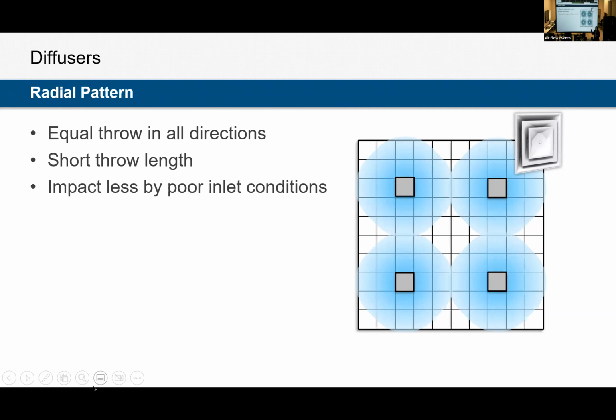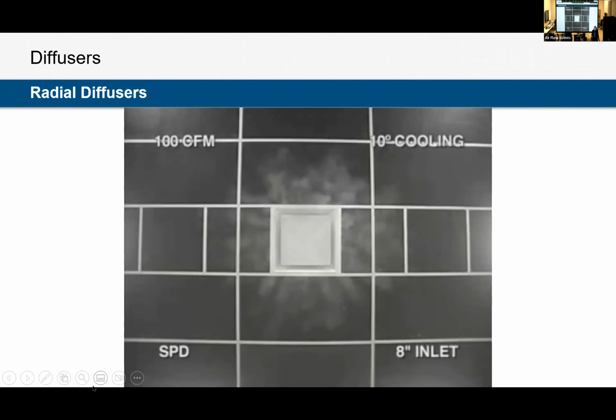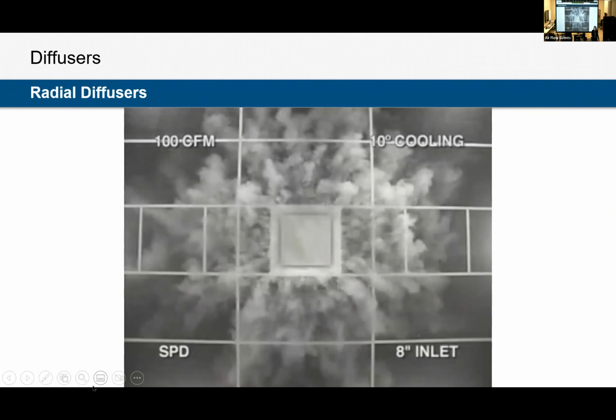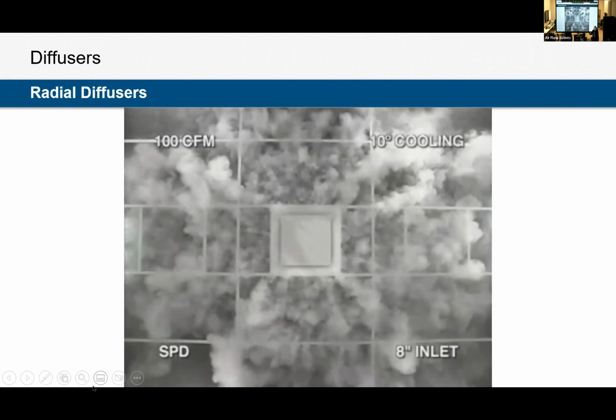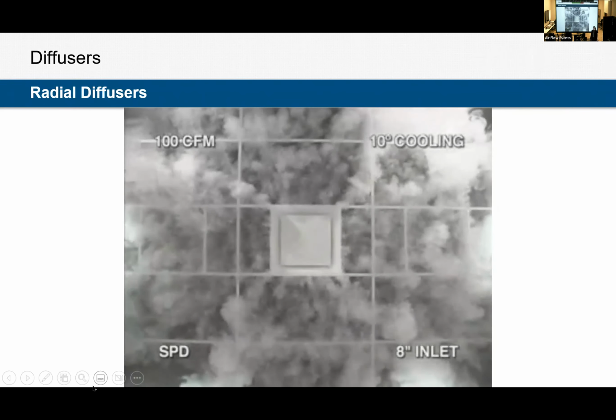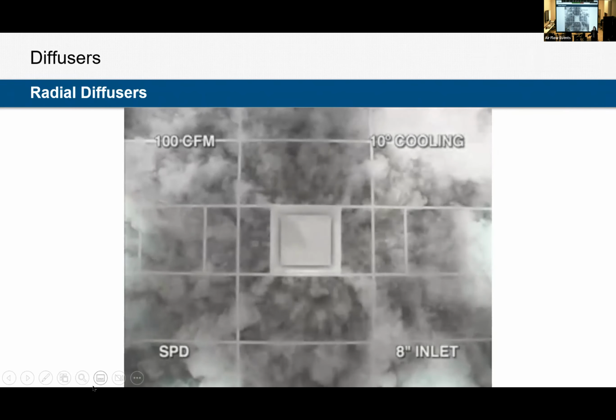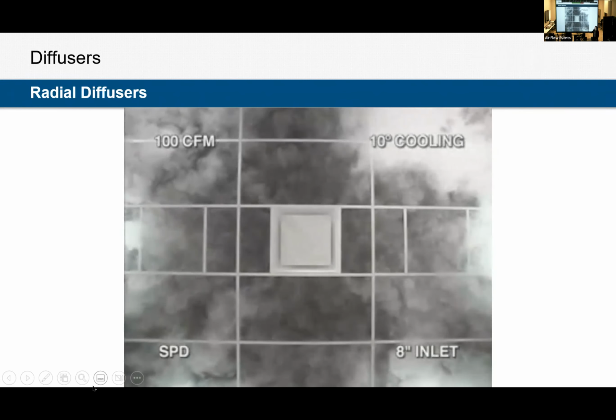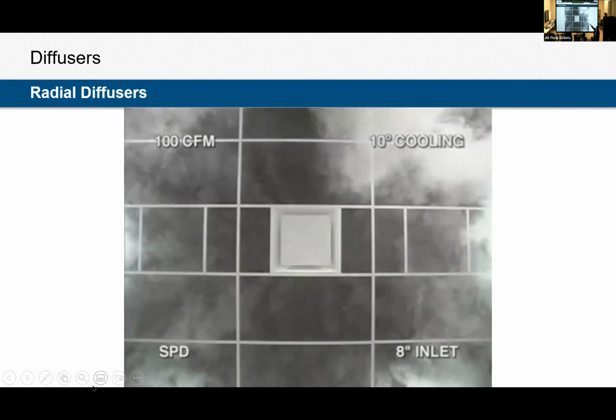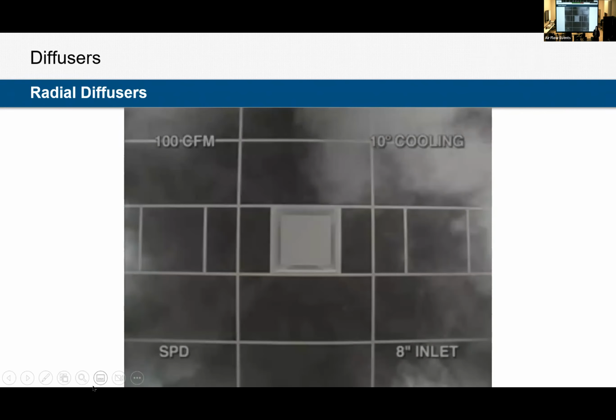So we can demonstrate this in the FlowViz room, but if you pump 500 CFM through one and then turn it down to 100 CFM, you'll get the exact same airflow pattern. It still will hug the ceiling a little bit before it starts dropping into the space. Not as much the case on a perf diffuser. I think I have an example of. Here's a smoke video of the square plaque diffuser. You can see that 360-degree release. And pretty quickly, we're going to start slowing down to our 50 feet per minute there at the edges.